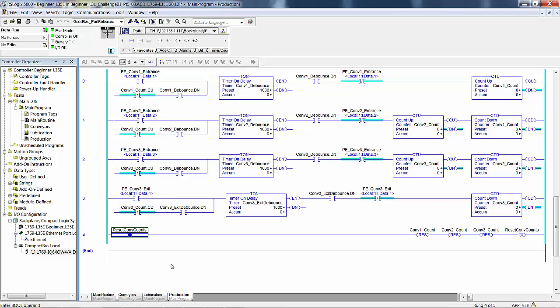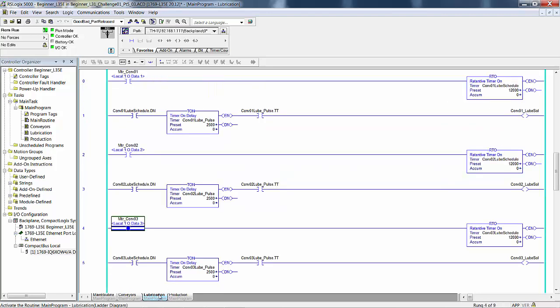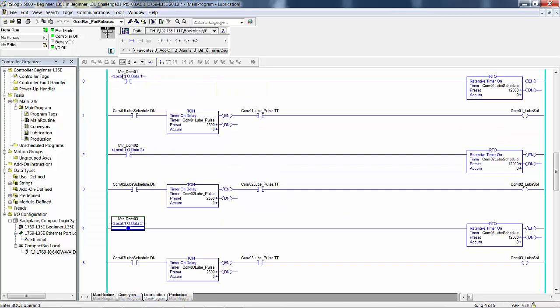Although we might not do this in the field, we are going to move the RTOs from the conveyor routine to the lubrication routine to make the logic more readable for the beginner. I already did that - if we go back to conveyors you see they were gone when we started this discussion because I had already moved them. If this motor bit is on then that rung is true, and the true state passes through that instruction to the RTO. We can examine this bit in memory, transfer it to the RTO, and I did that for all three loop schedules.